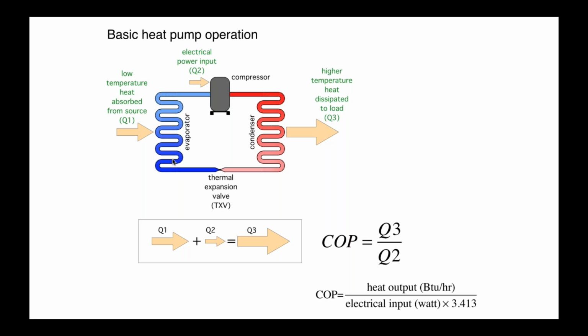So whenever that compressor's on, this circuit is operating continuously. And the measure that's used to gauge the efficiency is called coefficient of performance, or COP, and it's simply the ratio of how much energy is being delivered to the load divided by the rate of energy input to operate the heat pump, the vast majority of which goes into the compressor. So if we know the electrical input here in watts, we convert that to BTUs per hour, so we have the same units in the numerator and denominator. That's what a COP is.